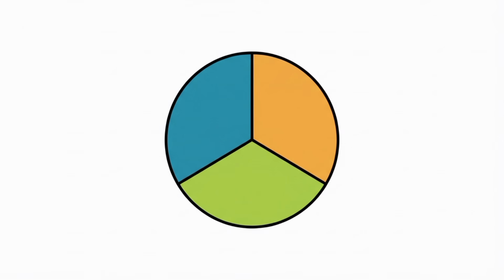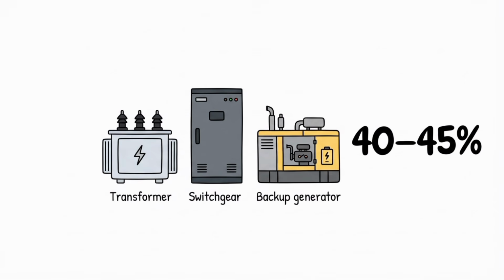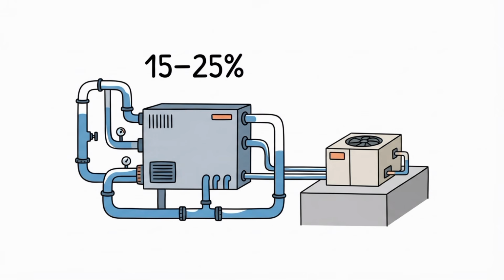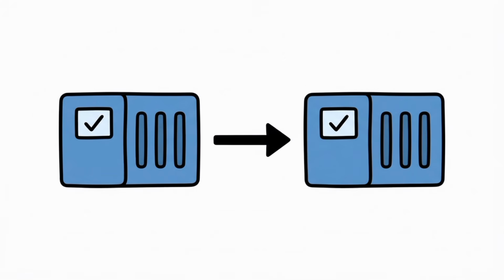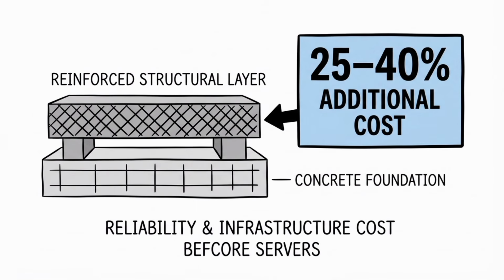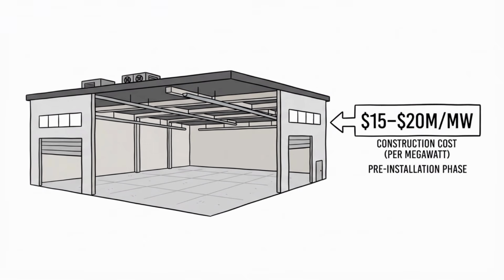Break the budget into its parts, and 3 cost drivers explain almost all of it. First, electrical systems — transformers, switchgear, backup generation — which eat 40 to 45% of the total on their own. Second, cooling, now 15 to 25% of the budget, up sharply from the days when a few rooftop units did the job. Third, redundancy, paying for a facility that never fully goes offline. Moving from a standard setup to the highest reliability tier adds another 25 to 40% by itself — insurance against downtime, priced into the concrete before a single server arrives.